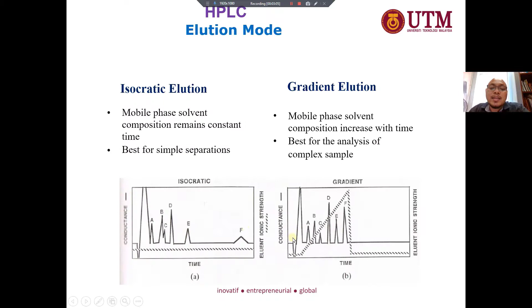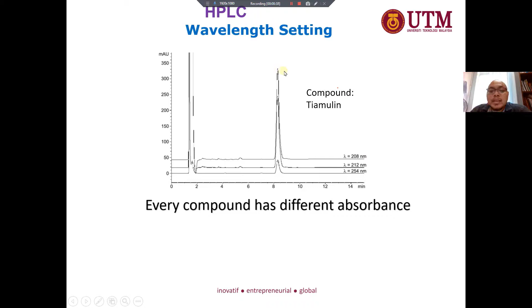Wavelength setting in the HPLC. I need to remind you that every compound has a different maximum absorption. If you look here, every compound has different absorbance. For example, the compound is Tiamulin. At 254 nanometer wavelength, it shows a weak absorption. At 212 and 208, their absorption is comparable. Maybe here it is only 212. At 208, the sensitivity is much better.